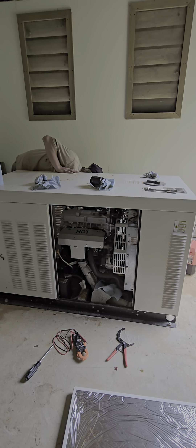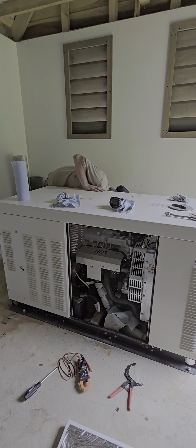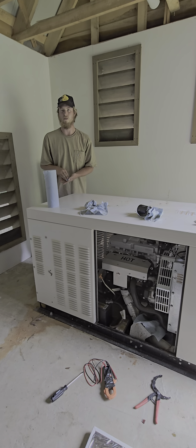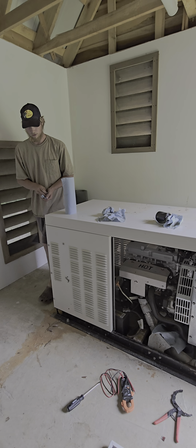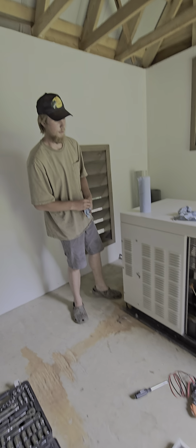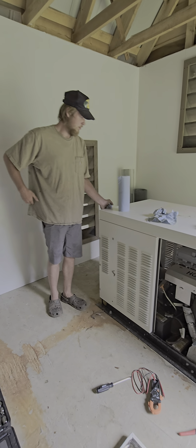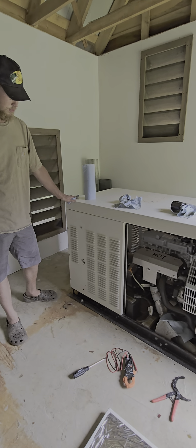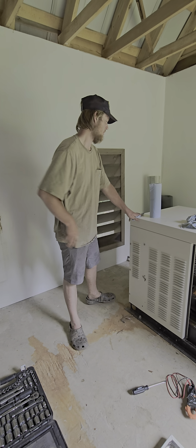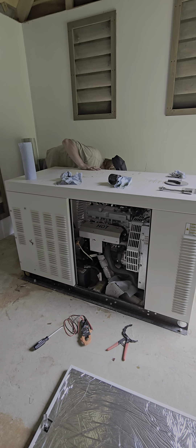It's been fabulous. The oil gets changed once a year, and we also inspect the battery to make sure it's charging properly. I checked it — it's charging the battery while running, so the alternator's working. We had a problem before where the original installer didn't run a wire correctly, so it wasn't charging the battery properly and we had a trickle charger on it — we never understood why. The trickle charger wasn't done properly. That company we got rid of and they never came back.